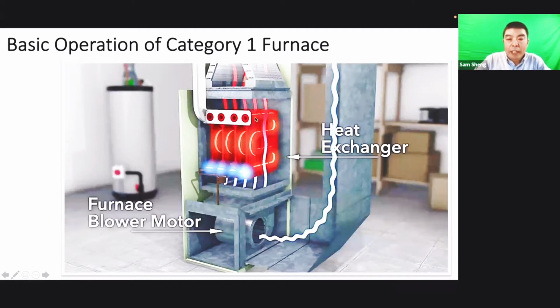Yeah. But if the heat exchanger is cracked, for example a crack here, a crack somewhere like from here, then when the blower motor is running, some air will blow into the tube. At that time we can see the flame roll out or be unsteady. If it is like that, we should know we need to check the heat exchanger, be careful.